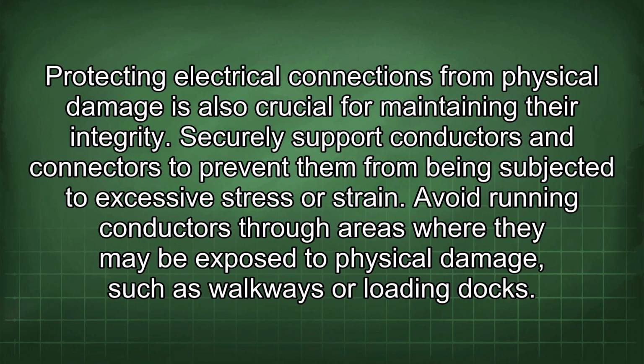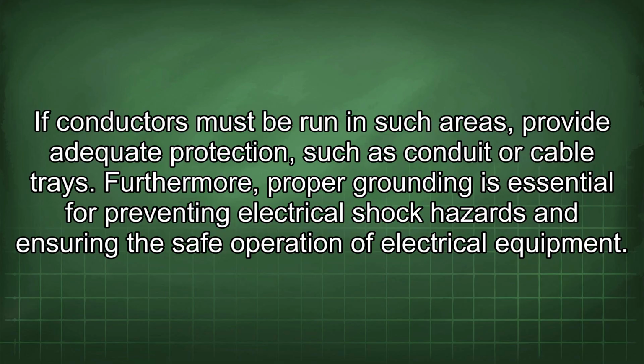failures. Protecting electrical connections from physical damage is also crucial for maintaining their integrity. Securely support conductors and connectors to prevent them from being subjected to excessive stress or strain. Avoid running conductors through areas where they may be exposed to physical damage, such as walkways or loading docks. If conductors must be run in such areas, provide adequate protection, such as conduit or cable trays.